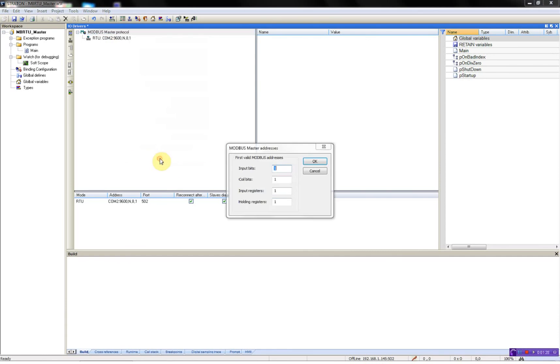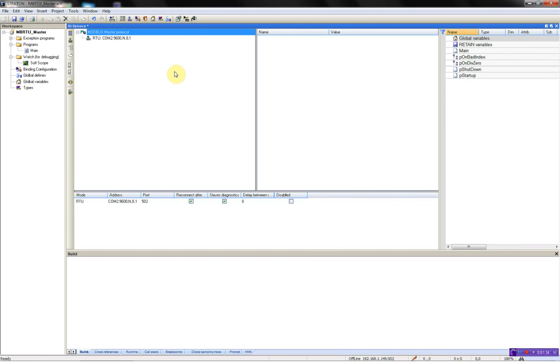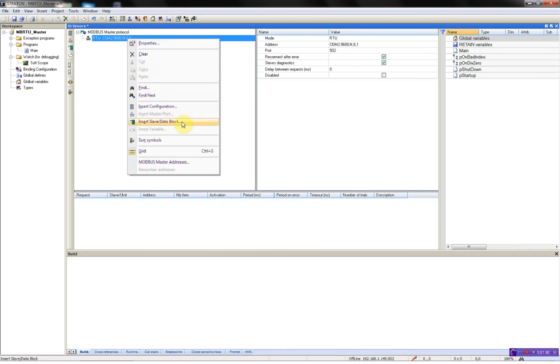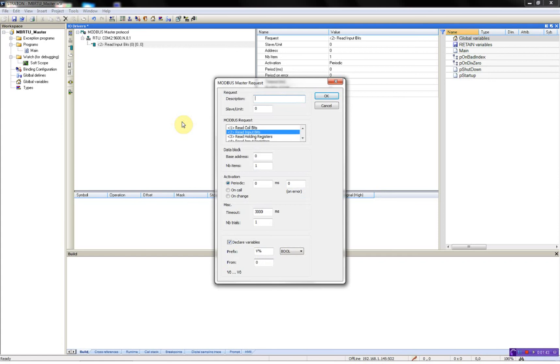I'll just set my indexes to zero. Now I can add my data points, which I'll be requesting from the slave. Enter slave data block: digital input, slave one. Read input bits, to 8, periodic, 200 milliseconds. I'll use the naming convention: slave one, digital input. Now the Straton workbench will create the variables automatically for me.